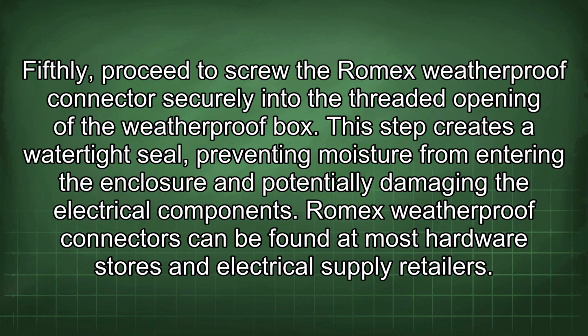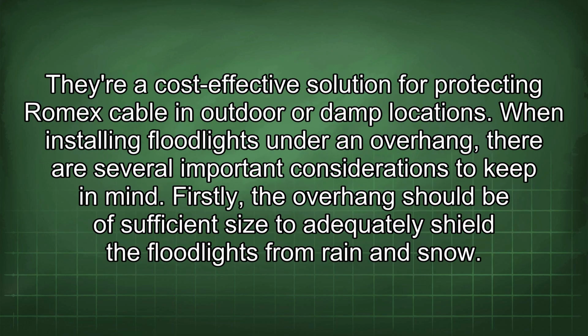Fifthly, proceed to screw the Romex weatherproof connector securely into the threaded opening of the weatherproof box. This step creates a watertight seal, preventing moisture from entering the enclosure and potentially damaging the electrical components. Romex weatherproof connectors can be found at most hardware stores and electrical supply retailers. They are a cost-effective solution for protecting Romex cable in outdoor or damp locations.